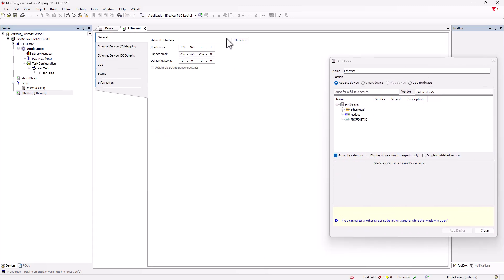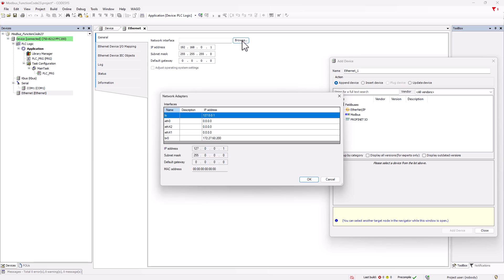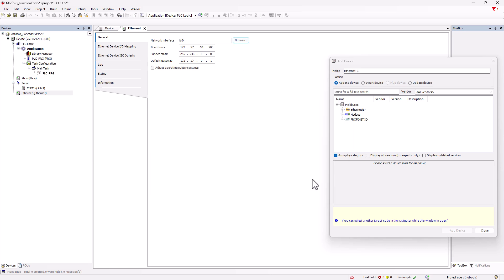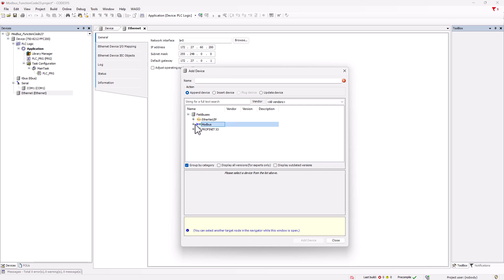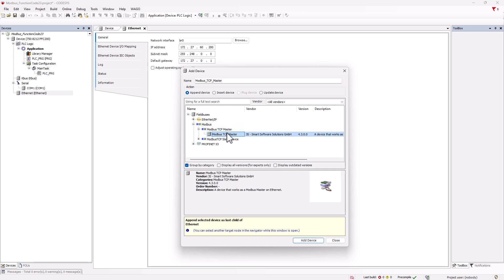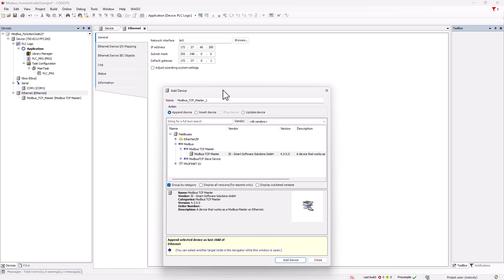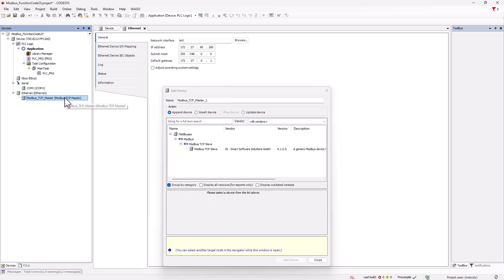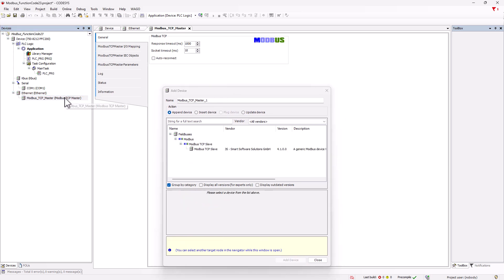We set up the network interface and connect the Modbus master to the Ethernet interface. At this point it is advisable to tick the box for auto reconnect so that the master automatically reconnects to the slave in case of a connection interruption.